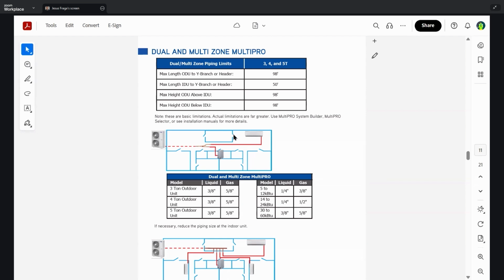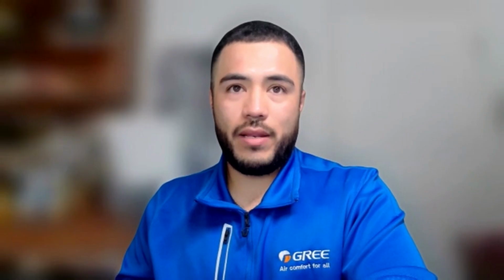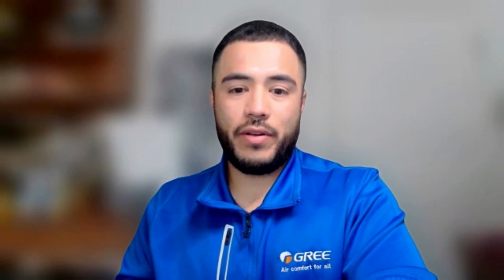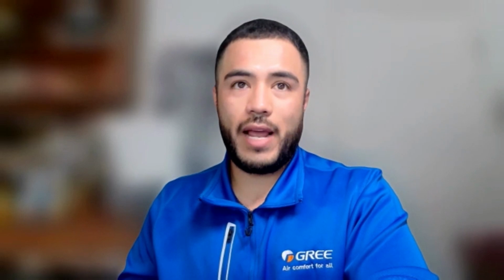So below is a basic limitation. Actual limitations are far greater. Use MultiPRO System Builder, MultiPRO Selector, or see installation manuals for more details. That's what I always like to mention, that we actually have the software on our GREE commercial site. It's a VRF selector. You can actually download it. It's free. And you punch in your outdoor units, your indoor units, and your copper lengths, and it'll actually give you whether it accepts the design and the additional refrigerant charge as necessary for your application.